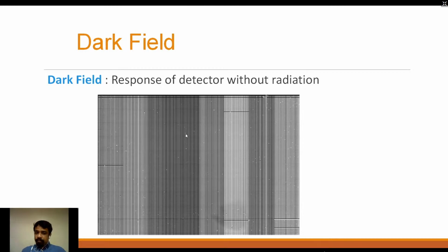These are the dead pixels, but still we can average in between, because these have a lot of pixels with a 0.3 mm resolution. We cannot expect all these detectors to work initially. Gradually, when it becomes 1 year and 2 years, we'll get a lot of dead pixels. But we have software which can average the pixel. Where there is a dead pixel, we can average it.